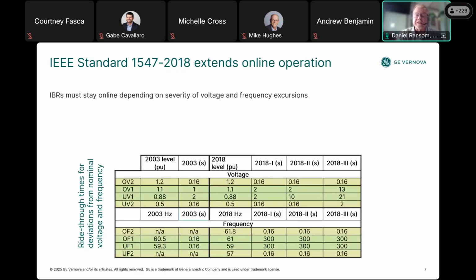Now, since 2014, a large influx of DERs, and this is mostly IBRs from wind and solar and battery energy storage systems, required updating to the present 2018 edition. It specifies waiting for the cessation of operation depending upon the severity, how far it deviates in frequency and voltage. The types, as you can see here, are the following. There's category 1, which meets the bulk EPS reliability, applies to all DERs, including rotating machines. Where it gets longer is in category 2.